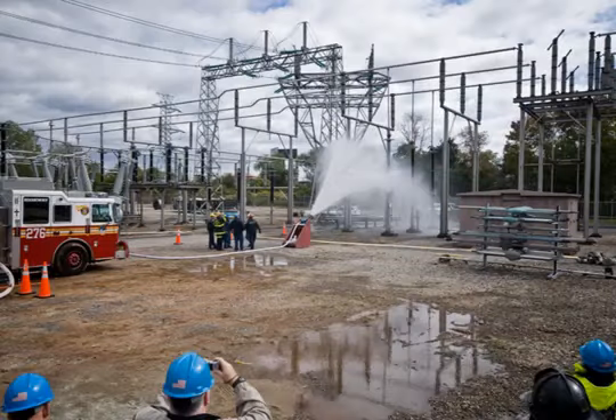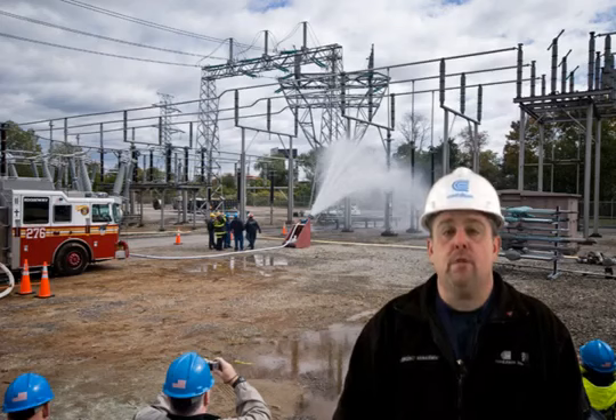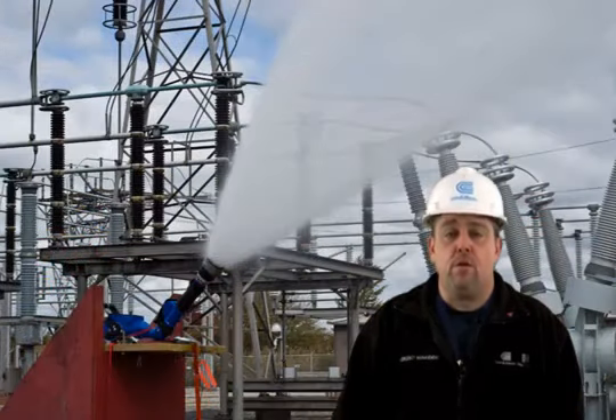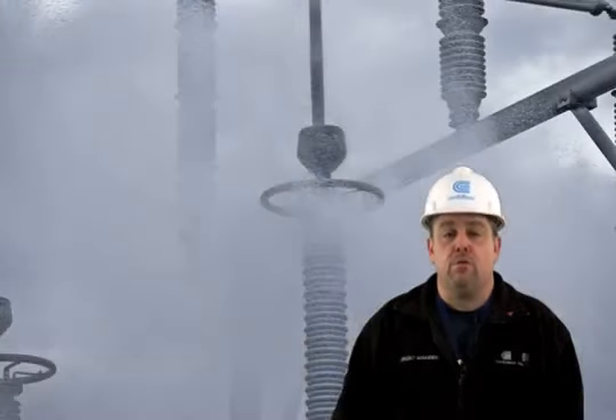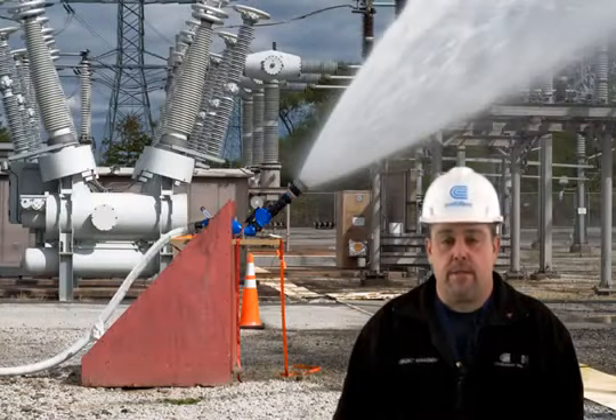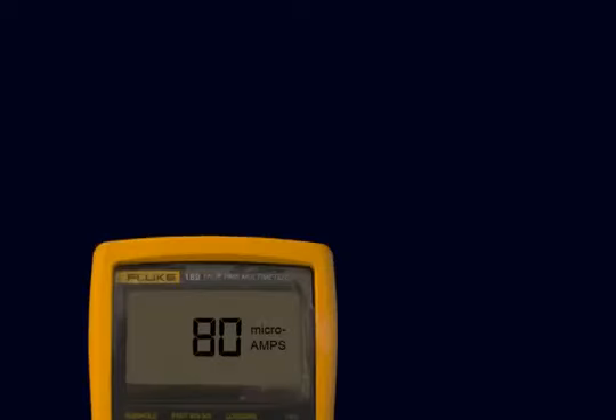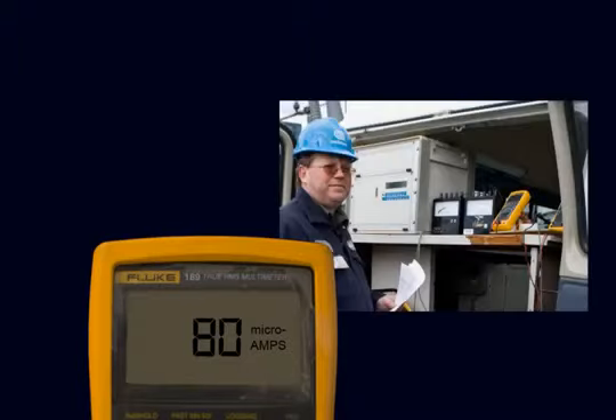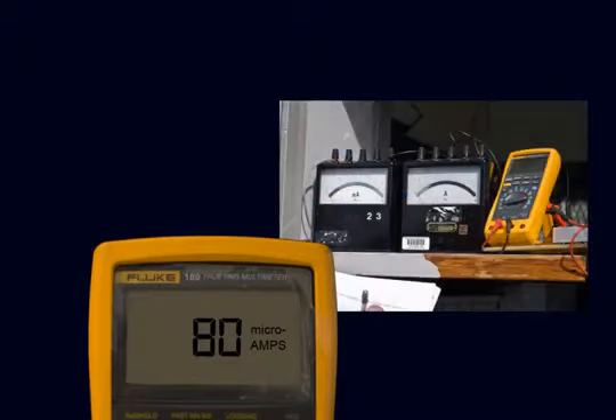In the first test, we used a fog pattern. F500 was delivered from a fog nozzle at a 30-degree pattern onto the 345,000 volt overhead conductors from a test stand. Leakage current back to the delivery nozzle was measured and recorded by our technicians during the test.